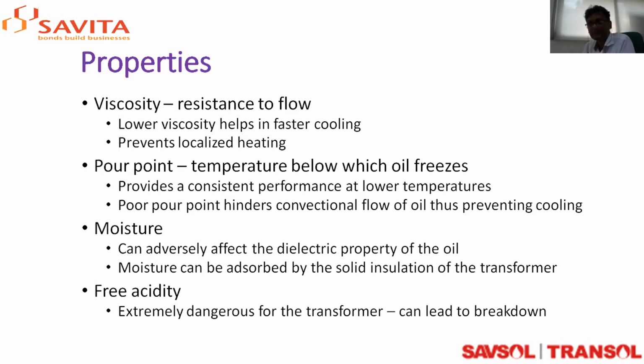Moisture is the most harmful molecule, impacting most properties of the transformer. When moisture is high, breakdown voltage comes down, which impacts the quality of the oil. It also deteriorates the paper, because mineral oil itself is hydrophobic and doesn't retain moisture. As soon as there is a larger amount of moisture, it dissipates into the paper, and the quality of the paper is hampered because of this moisture combined with high temperature.